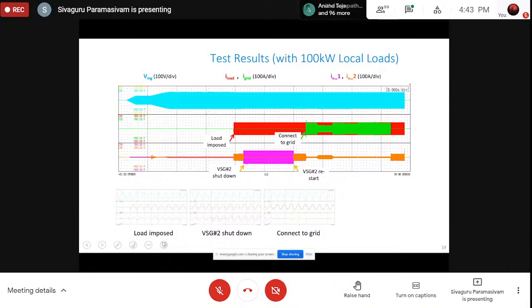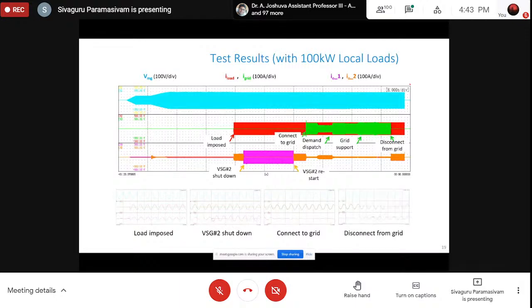And the VSGs restart, which means that after switching it off, you can see that in between the green has started, right? So we can see the grid is getting connected again, connect to the grid, and the demand dispatch is completed. So grid support, and then disconnect from the grid. So what I'm trying to explain from here is that when we are connecting to the grid and when we are disconnecting from the grid, the load doesn't suffer any problem. The load is as it is. It doesn't shut down. It doesn't take a dip. So with the help of these inverters, with the help of our power electronic advancements, irrespective of the grid coming and going back, we can have the electrical networks unaffected, and it could work seamlessly without any problem. That's what this is trying to explain.